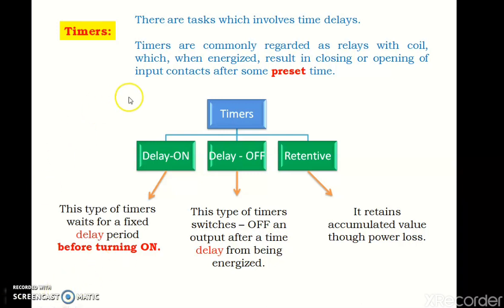Okay. Another timer is the delay off timer. This type of timer switches off an output after a time delay from being energized. It means after a certain time period, it will turn off and stop the output. Retentive timers retain the accumulated value. It means whatever value has been counted, it will be accumulated, even when there is a power loss. Okay.